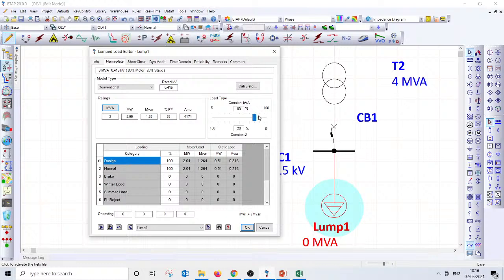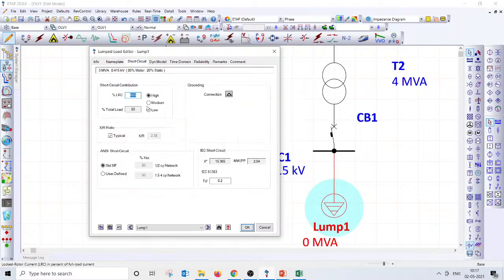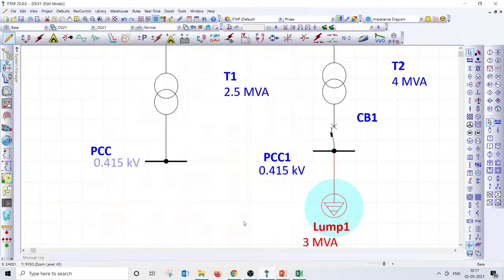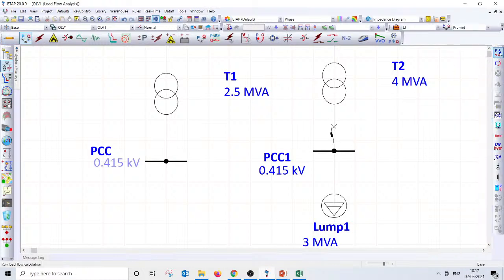If it is a commercial building, you will have predominantly constant current loads, like UPS and power electronic devices, like data centers. But if it is an industry which predominantly has motors, then there is always a probability that more than 80% of the loading on the transformer could be motor loads, and the remaining 20% could be static loads, right? And I'm also assuming the short circuit contribution from these motor loads is 6 times. This gives the worst of the worst case.